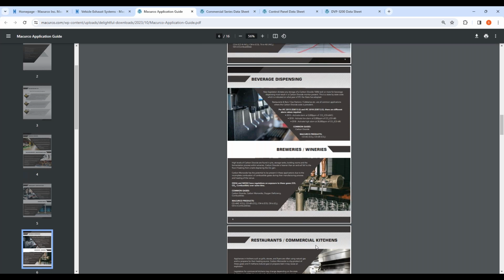Now, these are a lot of onesie twosies. I wouldn't recommend chasing these like crazy, but if you do land a Chipotle, a Costco type account, those are very, very prevalent, and those can be very, very large. But the code is very straightforward. Any time you have a 100-pound tank or more of CO2, they're required to have a CO2 monitor. A 100-pound tank of CO2 is not very big. It's no bigger than a scuba tank on your back if you go scuba diving. That's to give you a reference point.